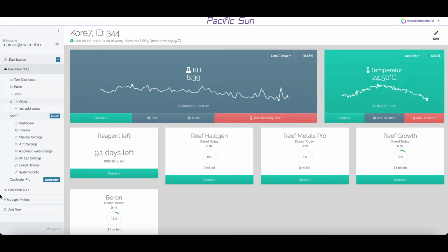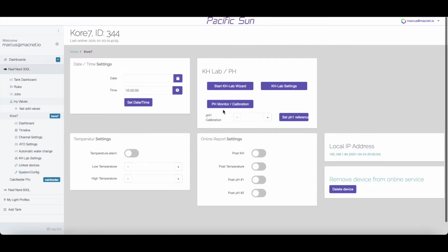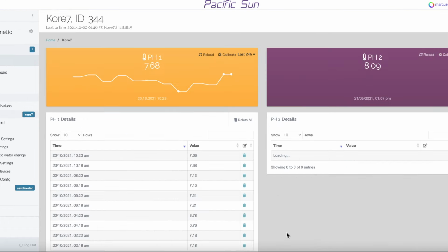So the process is to go to System Configuration down here, pH Monitor / Calibration, this button here. Then on this screen, what you're going to see is both of your pH probes. If one of them is not connected, there'll be no data available and you can ignore it. So in my case, I only have pH probe 1 connected, and it's saying that the pH is 7.68 right now, which we can ignore because we've not yet calibrated the probe.